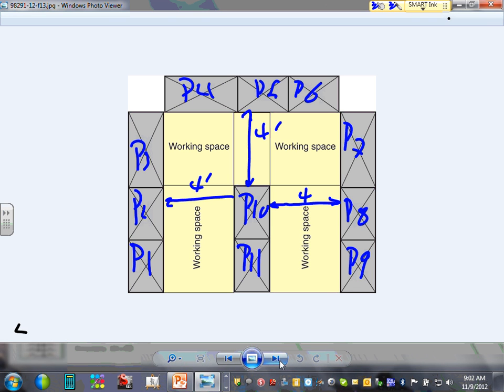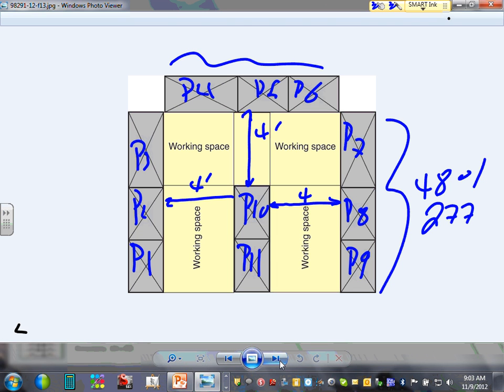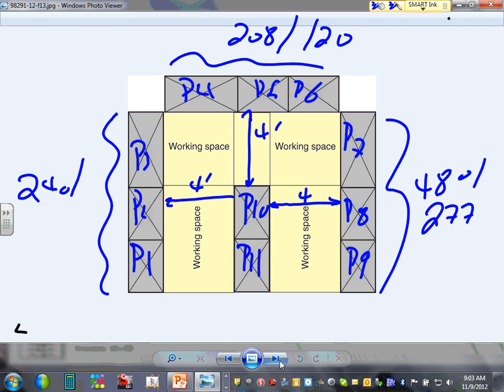All these are panels. And all of them are 1200 amps or less. You know why I said 1200 amps or less. If you put 4 feet around them, you're completely covered for all these conditions. And by the way, the voltages are, let's just say these guys are 480/277, right? These guys are 208/120, and these are 240/120. They're all 3 phase. Look at the voltages, right? So now you could have gotten on these ones 480 only. Delta. Any questions, guys, about this? 4 feet around, you're done.